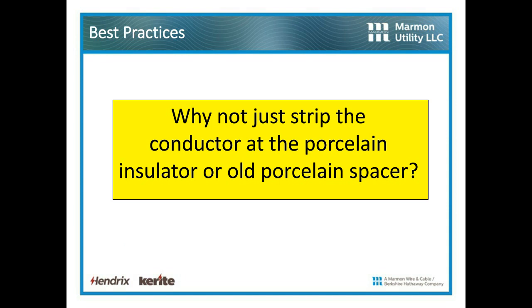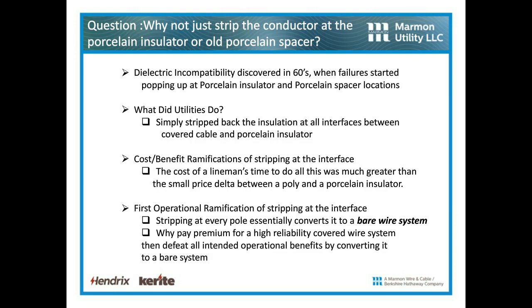This is the biggest one, I think. People say, well, why not just strip the conductor at the porcelain insulator and put my conductor there? Essentially, the industry discovered dielectric incompatibility in the 60s when failures started popping up at porcelain insulators and porcelain spacers. So what did the utility do? They said, okay, we finally believe you, you can't use porcelain insulators. So instead of changing them out to poly insulators, they simply stripped back the insulation at all interfaces between the covered cable and the porcelain insulator. The cost-benefit ramification of stripping at the interface on the first day was that the cost of the lineman's time to do all this stripping was much greater than the small price delta between a poly and a porcelain insulator. They could have just changed the insulator.